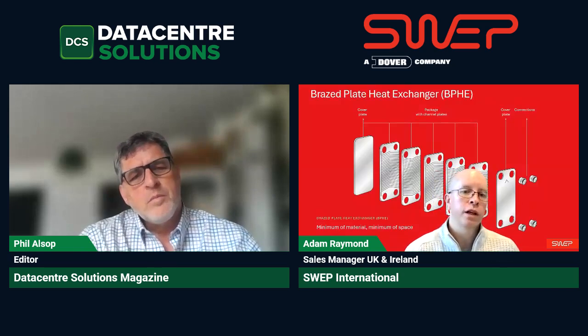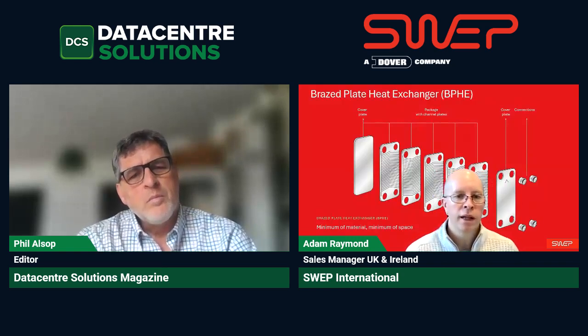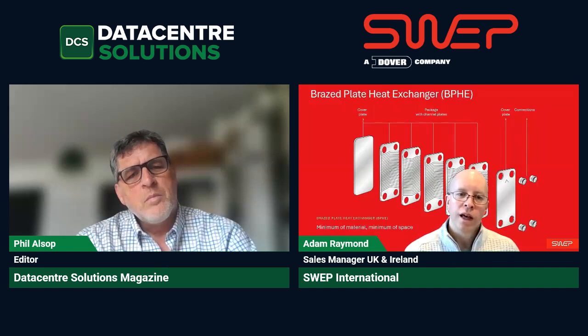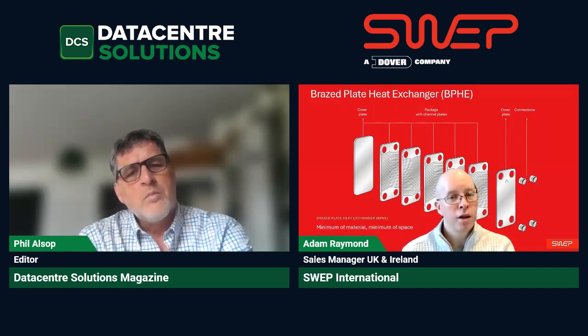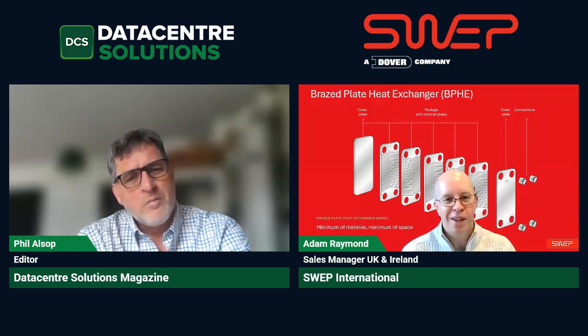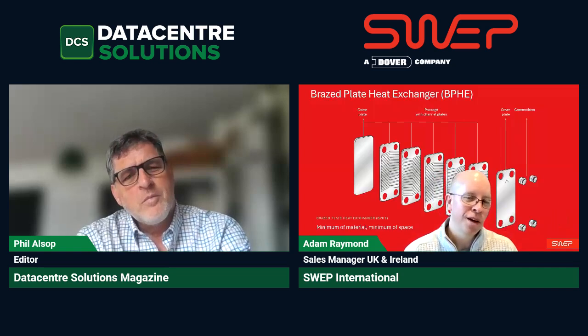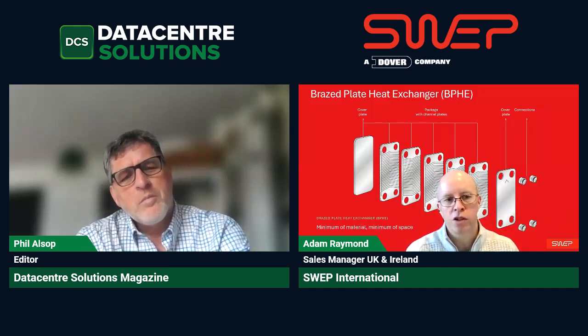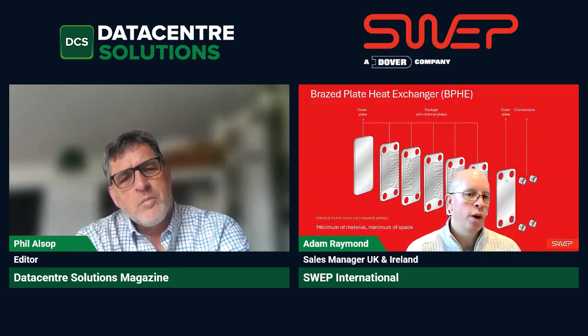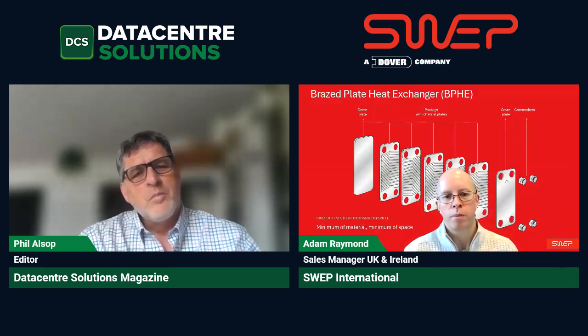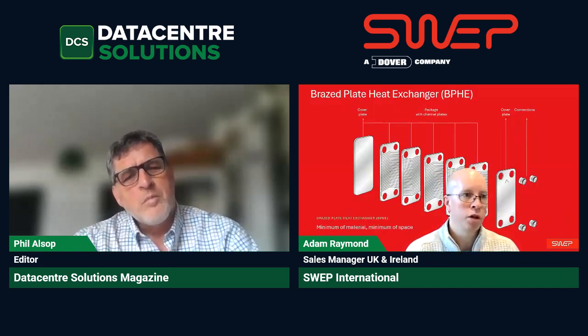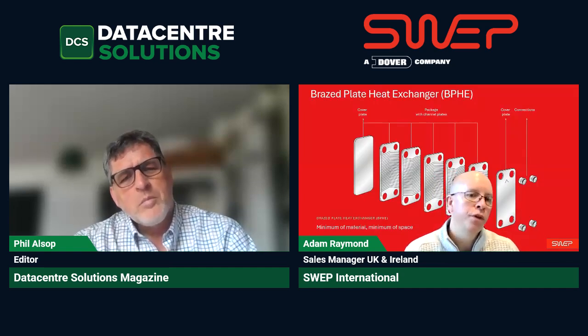So they've used the refrigerant heat recovery concept, but there wasn't anywhere locally that they could send that to easily in terms of direct heat consumers. So what they've actually done is sent it to a nearby wood pellet production facility. This waste heat, not particularly high temperature, is used to dry the pellets that are then burnt in a biomass plant for district energy. So in a way it's indirectly going to the district energy network, but through some different steps. The big challenge is connecting the place that has waste heat, the data center, to the consumer of waste heat, be that a local swimming pool, district energy, or commercial building. This is a difficult one to address.